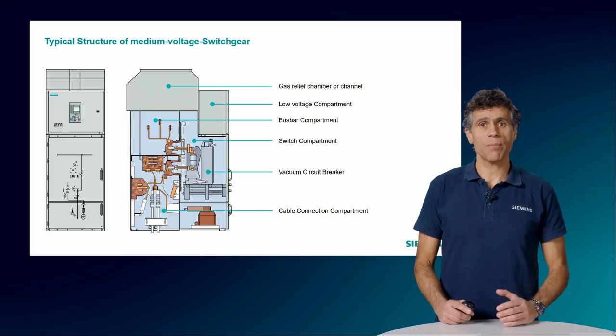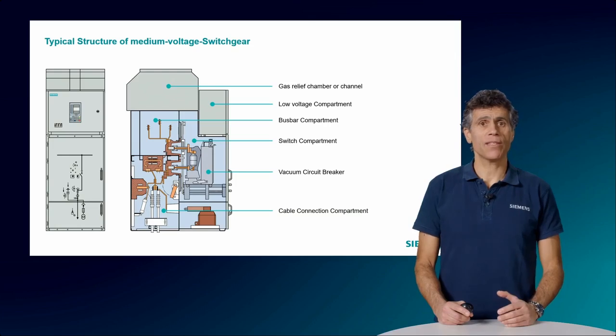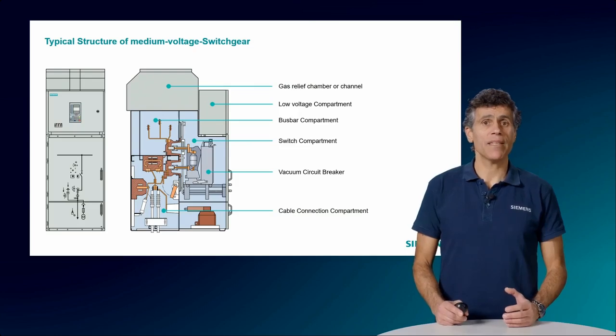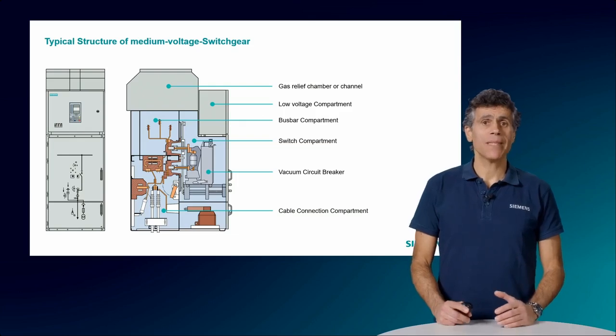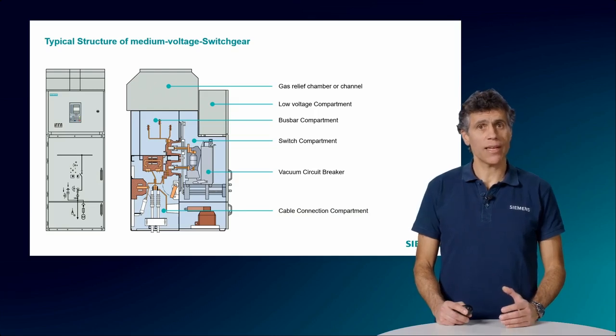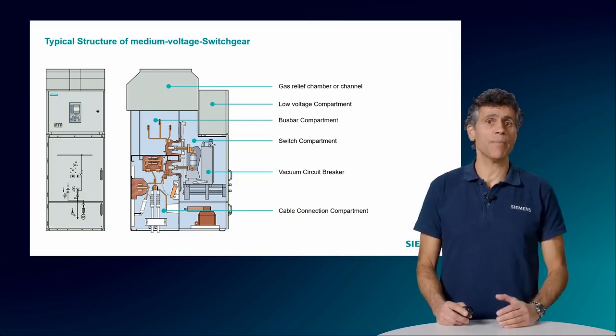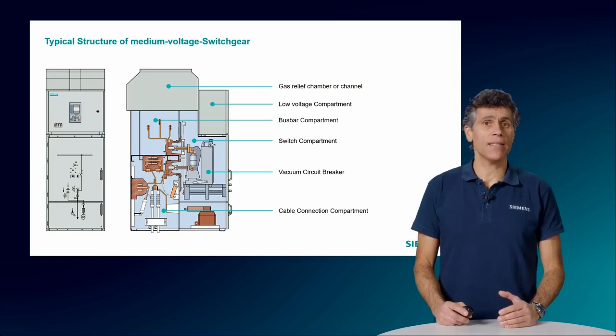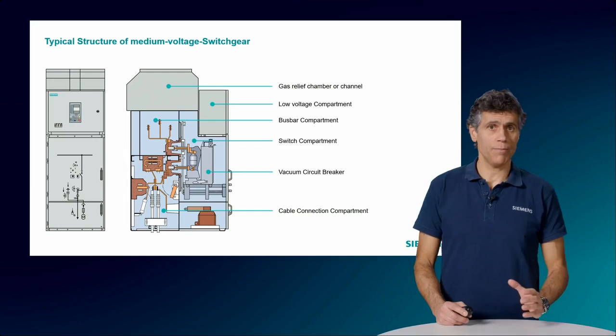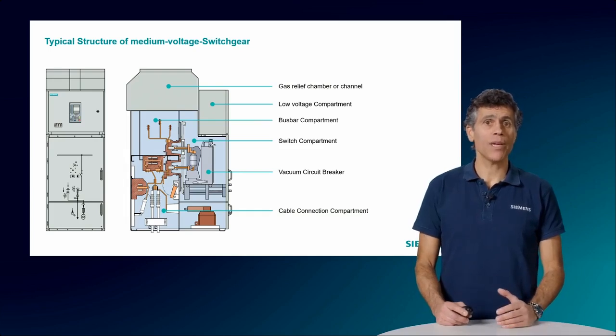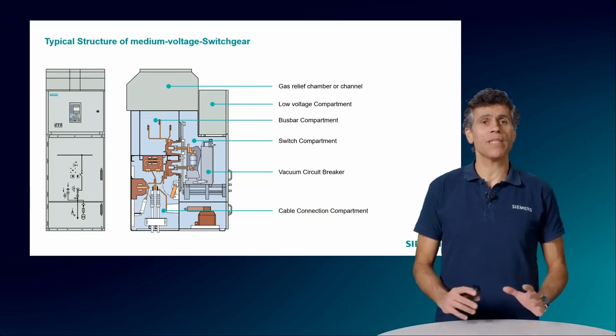And when you switch off the busbar, the whole switchgear has no power. If the breaker, however, has its own compartment and is accessible even when the busbar is connected to power, you can maintain a feeder without switching off all others. The type of compartmentalization of a switchgear is called loss of service continuity category, or shortly LSC. And here you see an example of the most demanding type of LSC, which is LSC2B. That means, in a very simple way, that each of the main functions of the switchgear has its own compartment independent from the others.